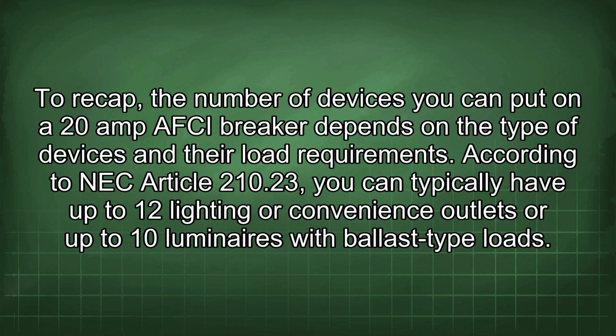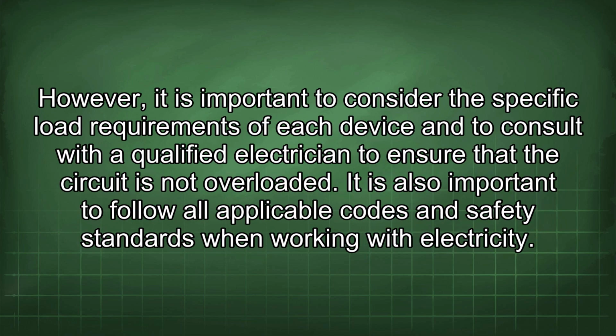To recap, the number of devices you can put on a 20 amp AFCI breaker depends on the type of devices and their load requirements. According to NEC Article 210.23, you can typically have up to 12 lighting or convenience outlets or up to 10 luminaires with ballast type loads. However, it is important to consider the specific load requirements of each device and to consult with a qualified electrician to ensure that the circuit is not overloaded.